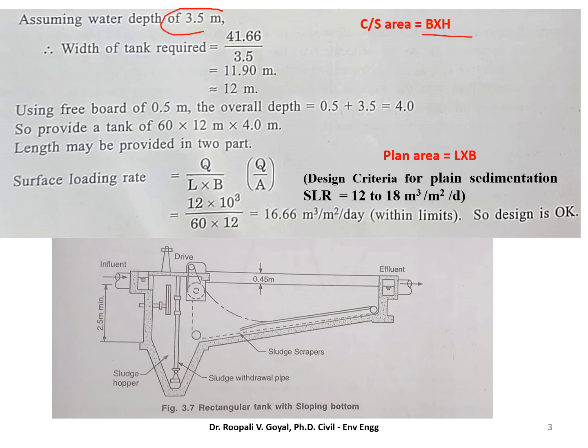So we assume water depth is 3.5 meter. So this cross sectional area divided by depth, it will give you your width of the tank. That is 11.9, and we are assuming it is 12 meter. Now we are using 0.5 meter as freeboard. So we assume total depth is 4 meter.